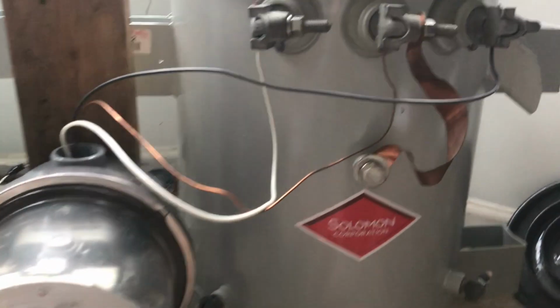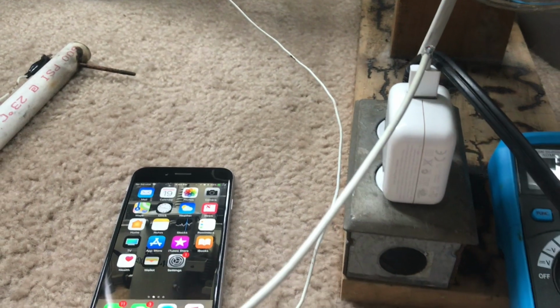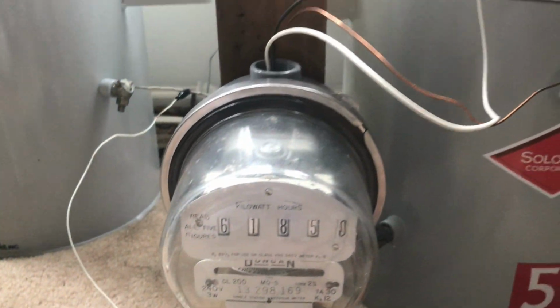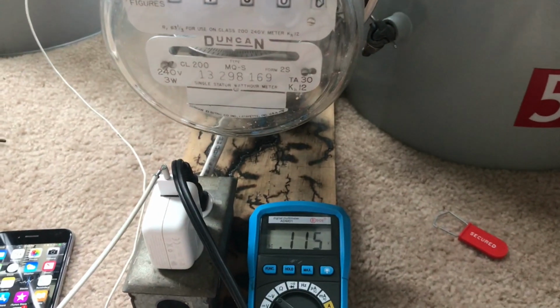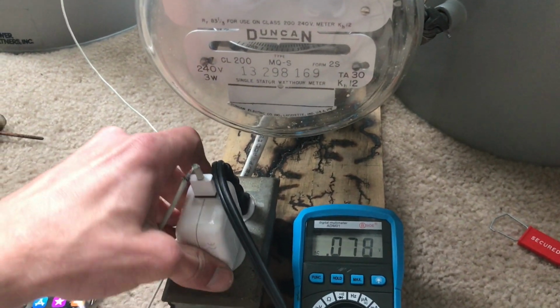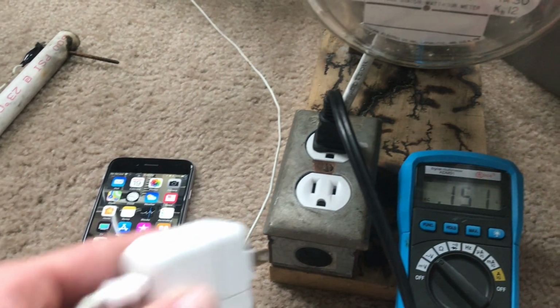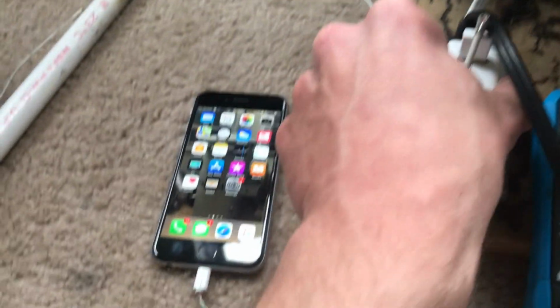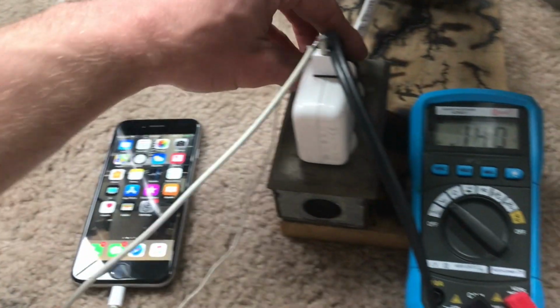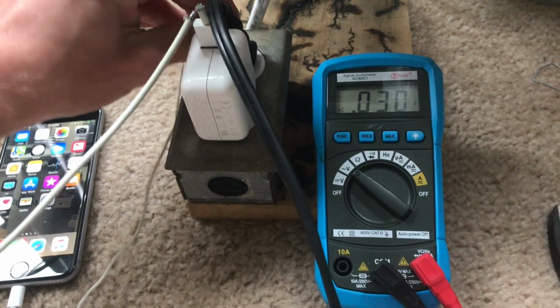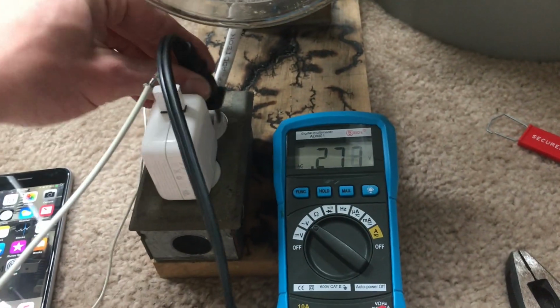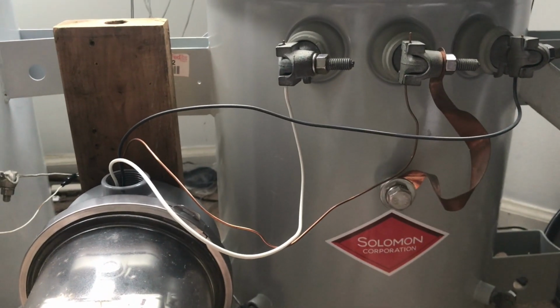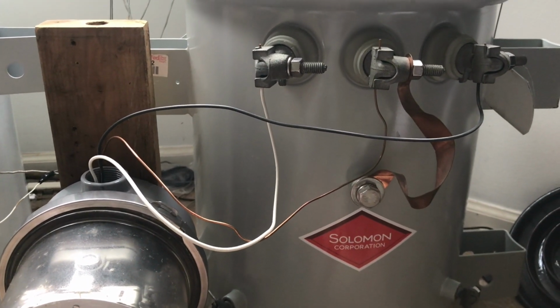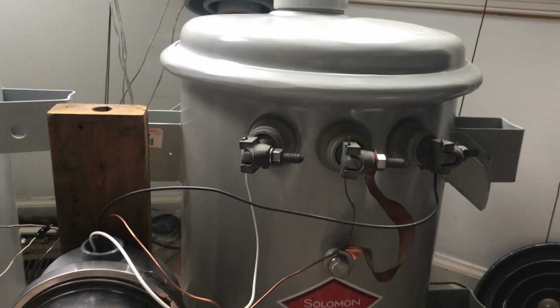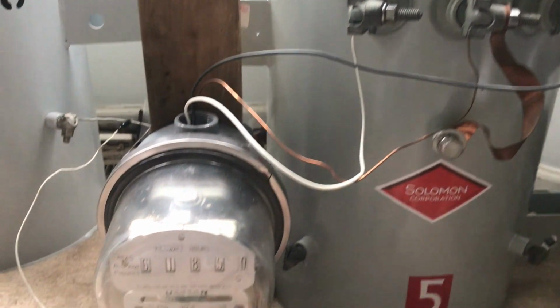As you can hear, the space heater turned back on and the iPhone started charging again. As you can see, both loads now can operate independently from one another. However, if the neutral was not there, you would have to put two 120 volt appliances in series for the 240 volts.